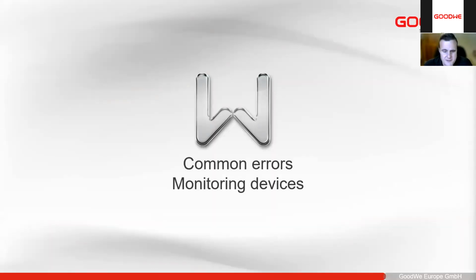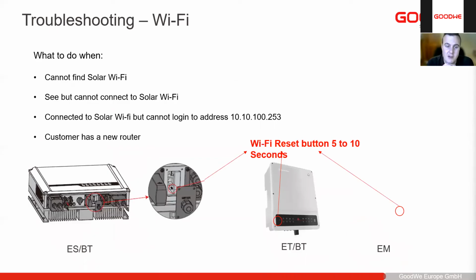Then we've got the monitoring devices. First off is our Wi-Fi. If you can see solar Wi-Fi but can't connect to it, or you can connect to solar Wi-Fi but can't enter the 10.10.100.253 address to log into the Wi-Fi module, or if the customer's network is no longer available and you're trying to connect to the device, there is the Wi-Fi reset button. On the ES, you'll see there is an internal reset button, but on all the newer ES models, we have the new Wi-Fi module that has it on the Wi-Fi module itself. On lots of our other inverters, ET, BT, EM, it is on the front screen.